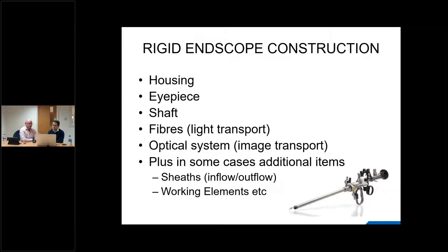The light system is made up of fiber light guide bundles — the fibers take light to the surgical site and the optical system takes the image back. The optical system can be one of three main types: a rod lens or rod lens hybrid with achromat system; a semi-flexible instrument using a coherent image guide fiber bundle where fibers at the proximal end correspond exactly to those at the distal end; and finally chip-on-the-tip instruments with a CCD chip at the tip sending back electronic images.